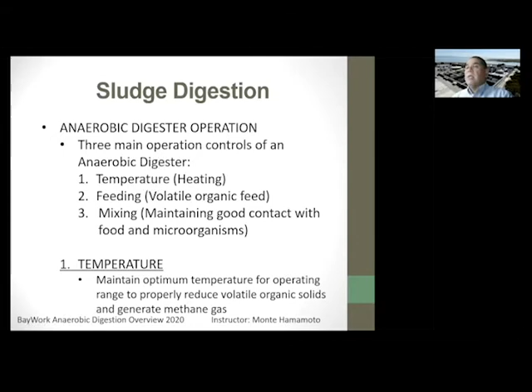The temperature, again, you want to maintain the optimum temperature, and you want to make sure that temperature is maintained so you can properly reduce those volatile organic solids, and so the temperature is right for those delicate methane formers. Feeding, you want to maintain the proper balance of volatile acids and methane fermentation. Basically, you don't want to feed so much volatile acids that it produces so much acid that it uses all of that alkalinity buffer that you have.